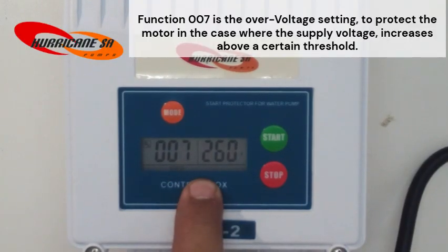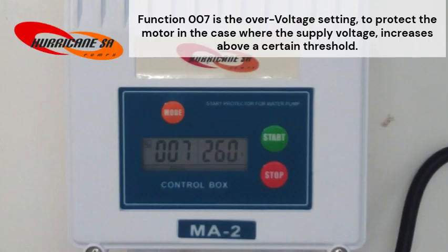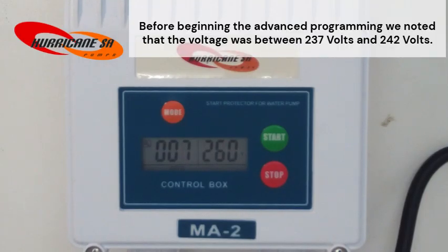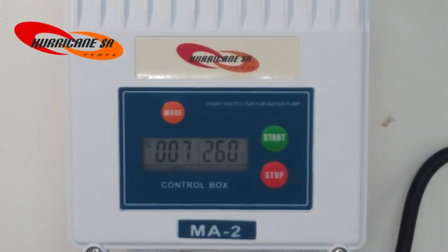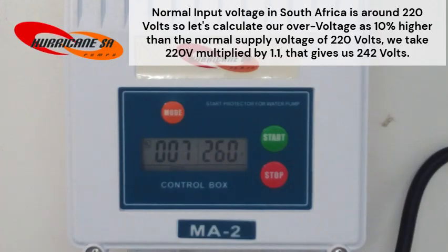Function 007 is the overvoltage setting to protect the motor in the case where the supply voltage increases above a certain threshold. Before beginning the advanced programming, we noted that the voltage was between 237 volts and 242 volts. Normal input voltage in South Africa is around 220 volts, so let's calculate our overvoltage as 10% higher than the normal supply voltage of 220 volts. We take 220V multiplied by 1.1. That gives us 242 volts.